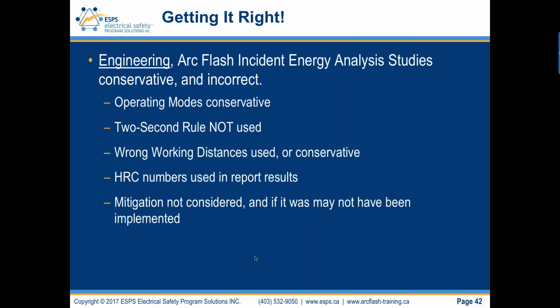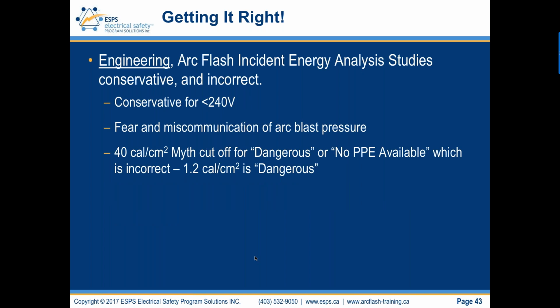So again, this is the challenge that we're faced with these studies. Conservative interpretation for less than 240 volts still with arcing fault probability. So that needs to be worked. And IEEE 1584 isn't necessarily going to provide all the information you need. So you're going to have to review that in more detail. Fear and miscommunication of arc blast pressure. In training, and that's where training that's been provided as awareness level training or other training is fear-based. And again, I don't sponsor that fear-based training. It's not solving the problem. It's not helping the workers.